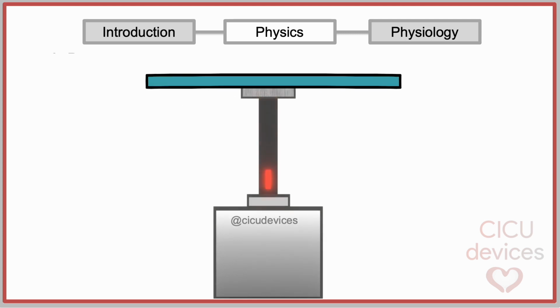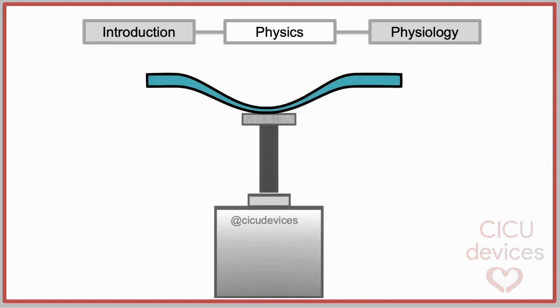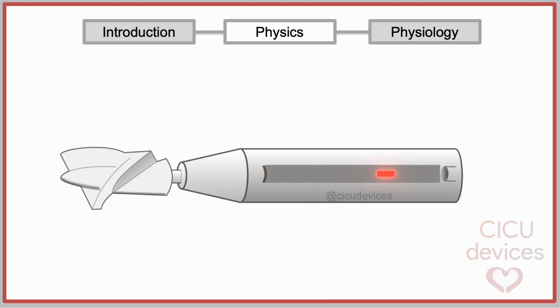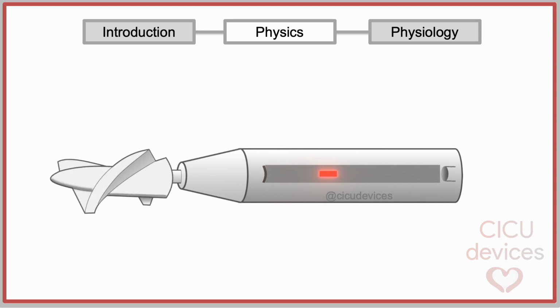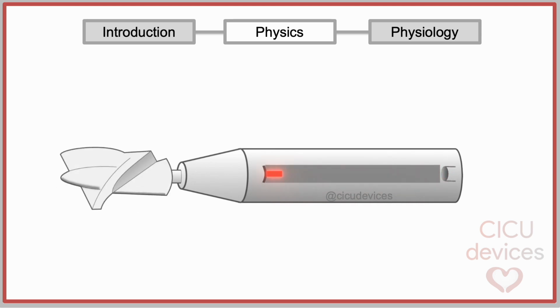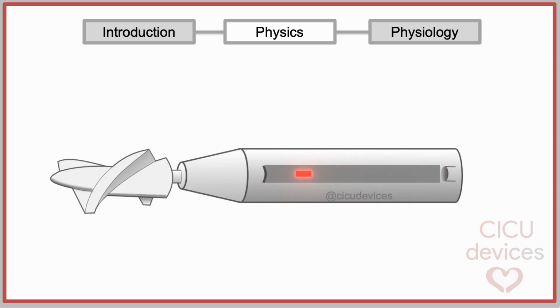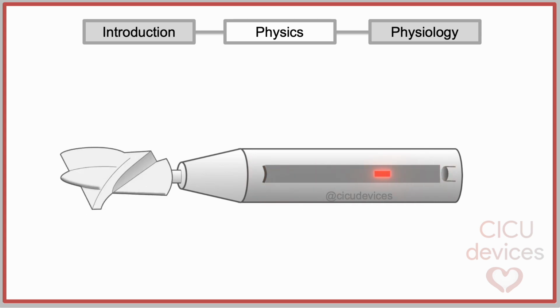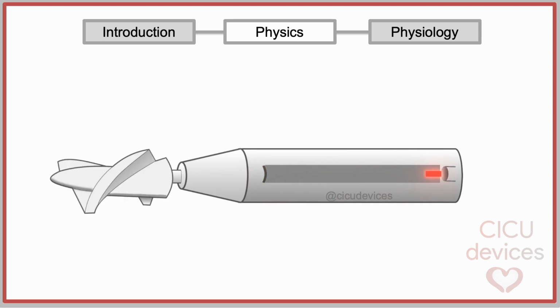In the following animation, we can observe the phenomenon in motion. We could consider this equilibrium position as zero pressure. If pressure is applied to the diaphragm, the distance traveled decreases proportionally to the exerted pressure. This small variation can be detected with great precision by laser. An algorithm correlates the difference in distance with the pressure received by the diaphragm. This system is integrated into the catheter and allows for establishing real-time, highly reliable blood pressure.